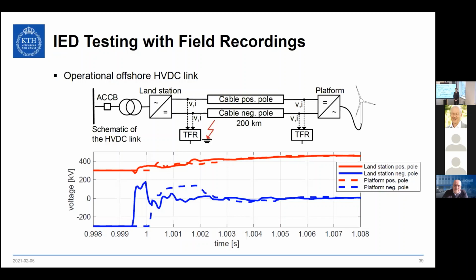So what happens in a DC side short circuit is that at some point this short circuit draws current coming from the connected cables, and ultimately through the converter from the AC side. So there's a high, rising current flowing through the converter, and if this current goes above the capabilities of the semiconductors, the converter blocks the cells and bypasses them, meaning in a half-bridge case it's no longer controllable, and you can't support reactive power to the AC side.